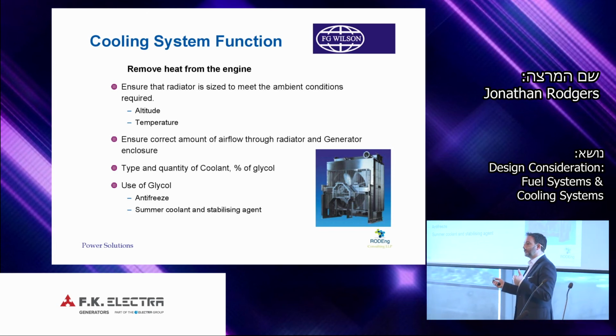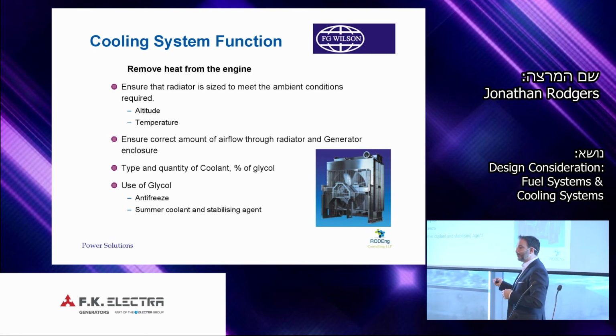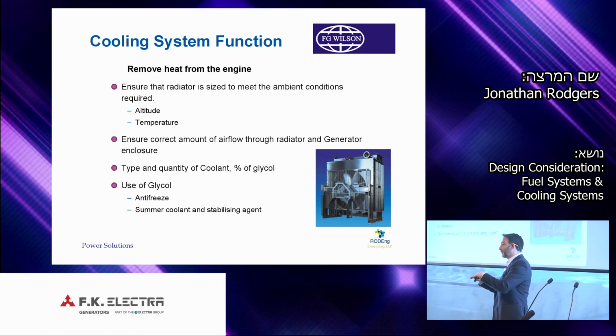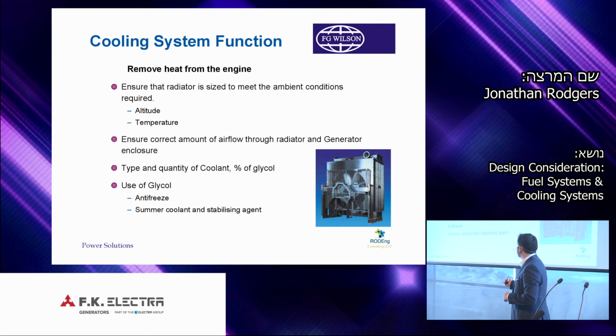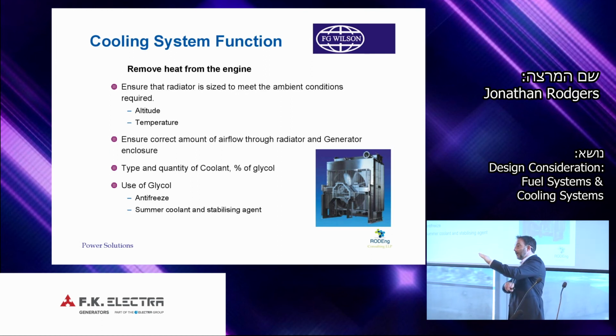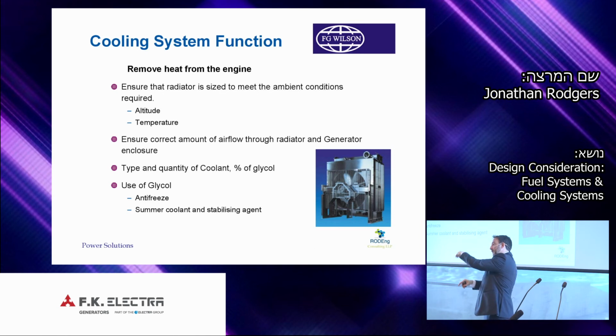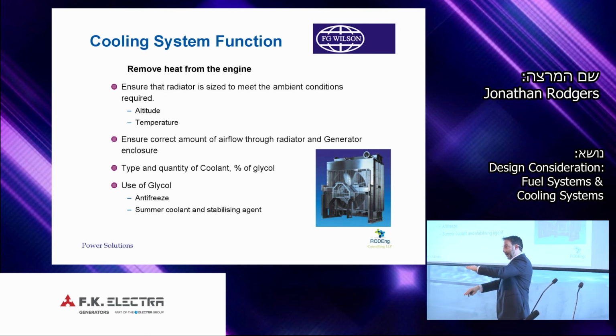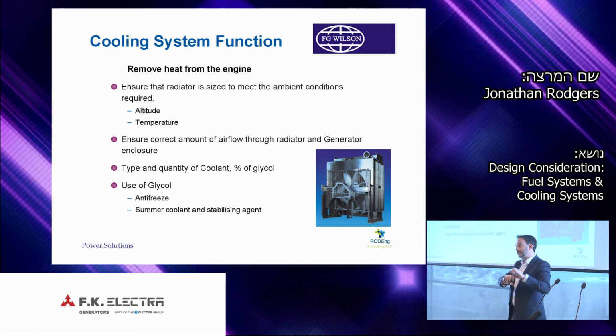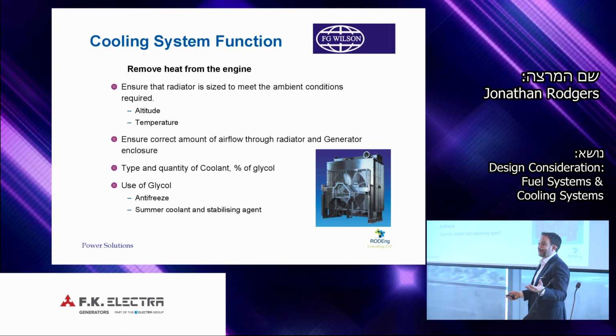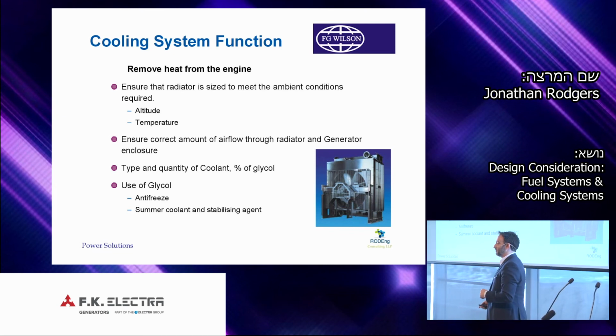The reason is that the glycol is not just an antifreeze. It's used as a stabilizing agent to stabilize the thermodynamic performance of the liquid, the coolant fluid. This is because with engines and generators, as you ramp up in load, the thermal output lags behind. As the engine drops in load, the thermal performance can still be climbing, lagging behind. And as the engine goes up and down in load, that thermal change can be significantly higher. So we use glycol as a stabilizing agent to keep the lag closer together, and it means you can have a much more efficient cooling circuit. So basically, if you take a standard FG Wilson generator and put it somewhere very hot, make sure it still has the glycol concentration because it affects the cooling.